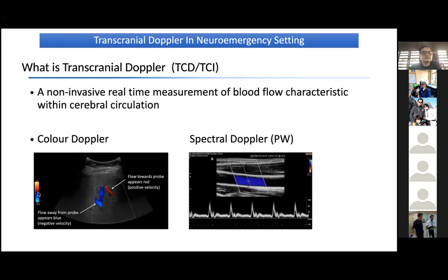Looking at the marker here, if the flow is almost 13 at maximum, it will be colored yellow. Somewhere around 5 to 6 will be red. If the flow is going away from the ultrasound beam or the transducer, it will be colored blue, and light blue if the velocity is higher. The information you get from color flow in transcranial Doppler is where the MCA is. Once you find the MCA, you put a sample inside it, and you get the representation of this velocity over time. So you get the spectral Doppler.